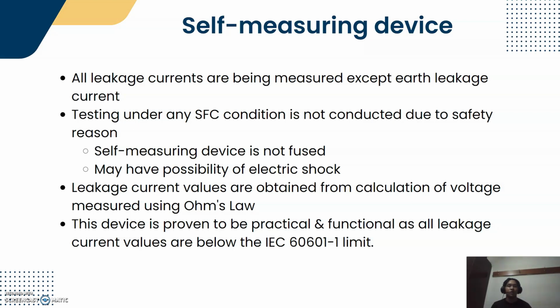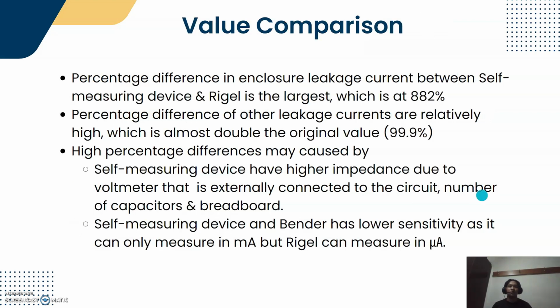IEC 60601 limit. To compare all these values, the percentage difference in enclosure leakage current between the self-measuring device and the Rigel is the largest, at 882%. The percentage differences of all other leakage currents are relatively high, almost double the original value at 99.9%. These high percentage differences may be caused by the self-measuring device having higher impedance due to the voltmeter that is externally connected to the circuit, the number of capacitors used, and the breadboard.